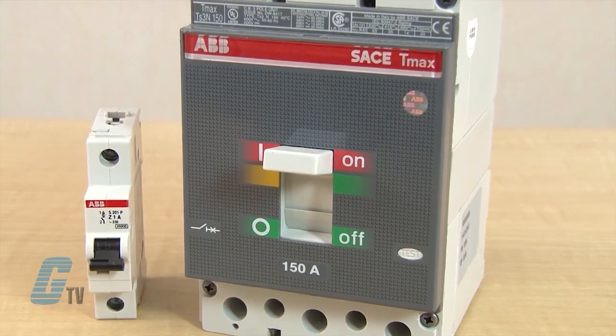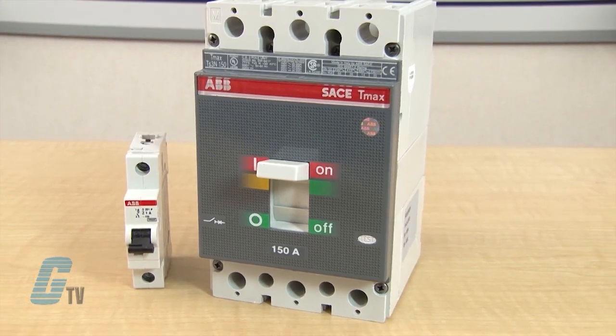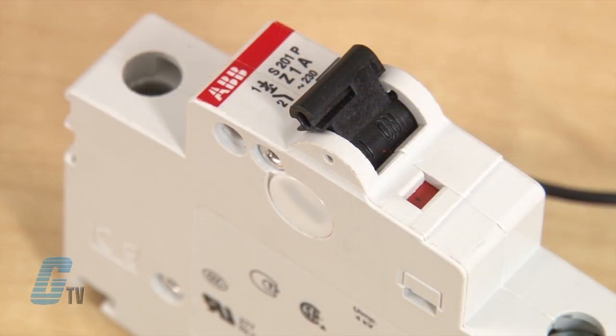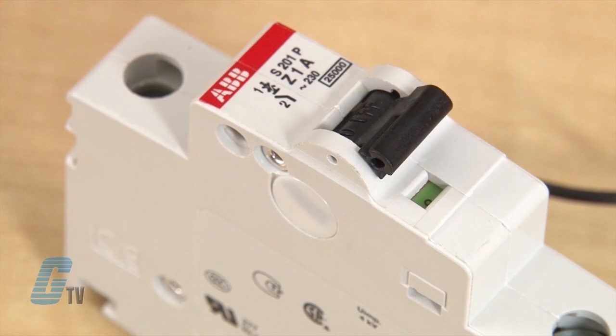Circuit breakers use a set of contacts to complete the circuit. The switching mechanism has a metallic lever that can be actuated by a solenoid or a bimetallic plate. With magnetic circuit breakers, the short circuit current charges the solenoid, attracting the metal lever that trips the device.